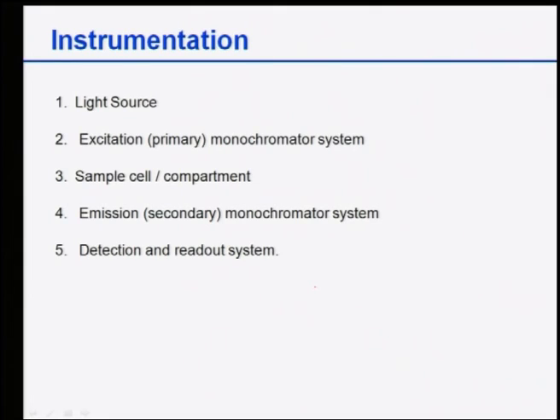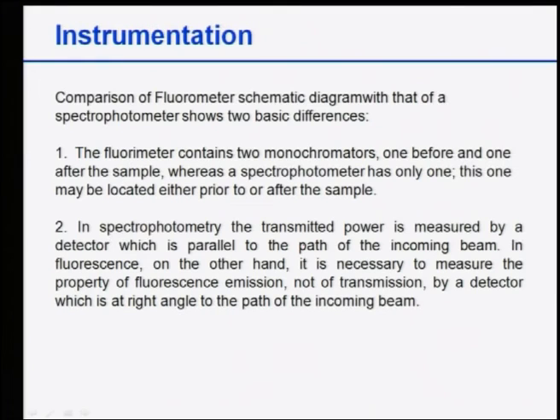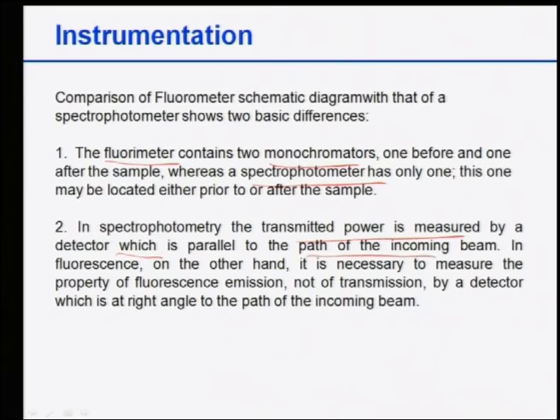For instrumentation in photoluminescence spectroscopy, five components are needed: a light source, excitation monochromator system, sample cell compartment, emission monochromator, and detecting system. A fluorometer contains two monochromators — one before and one after the sample (one for absorption, one for fluorescence) — unlike a spectrophotometer which has only one. In a spectrophotometer, transmitted power is measured by a detector parallel to the incoming beam, whereas in a fluorometer, the fluorescence emission is measured at a right angle to the incident beam.